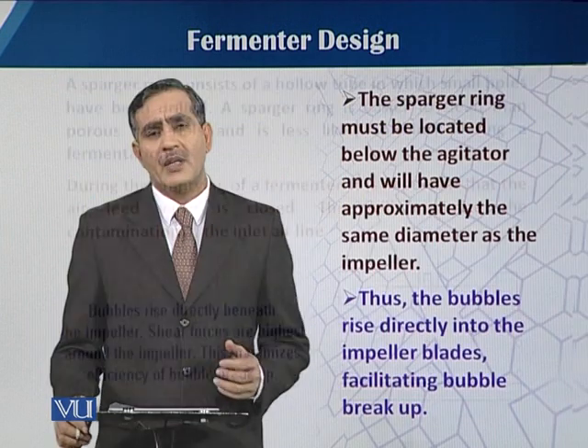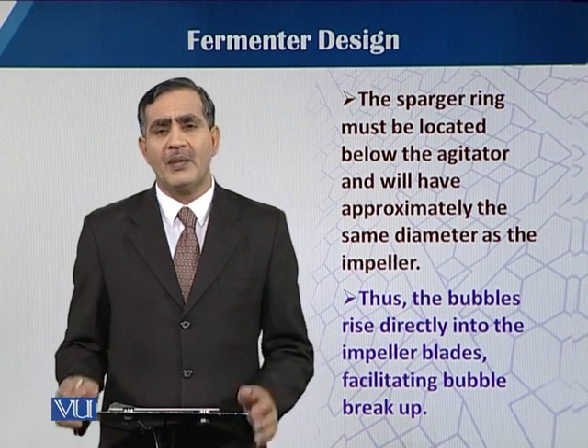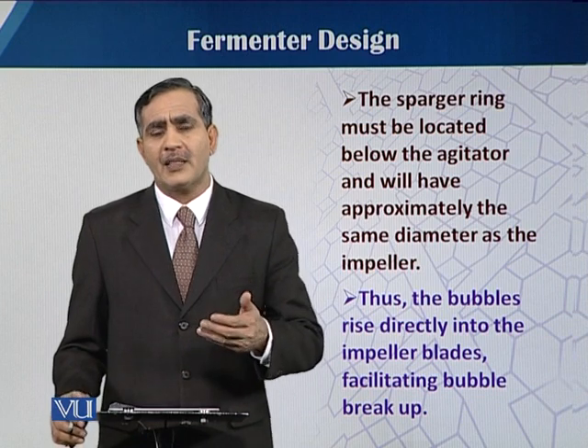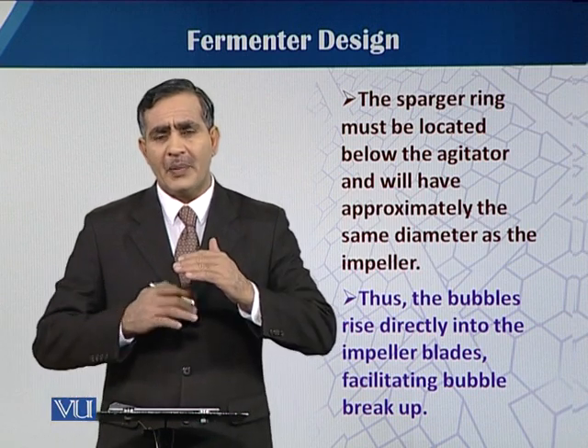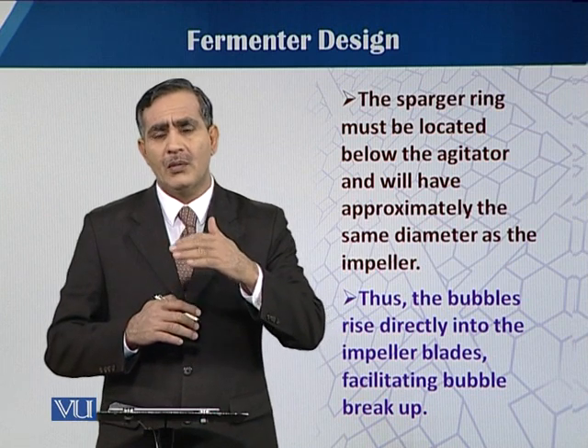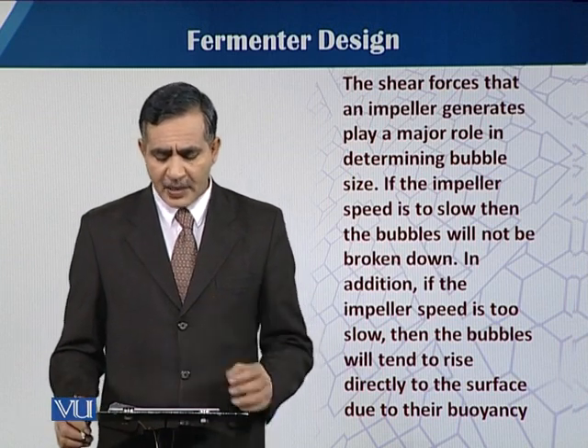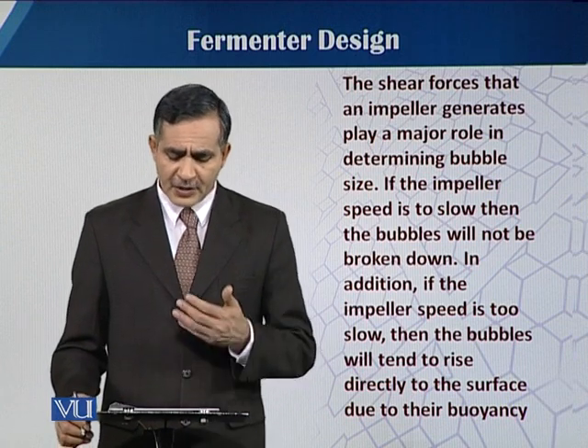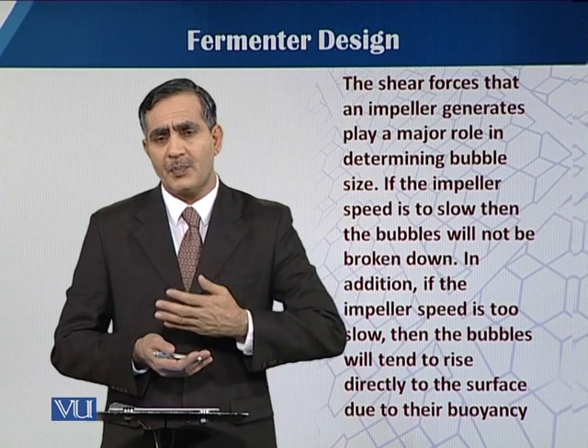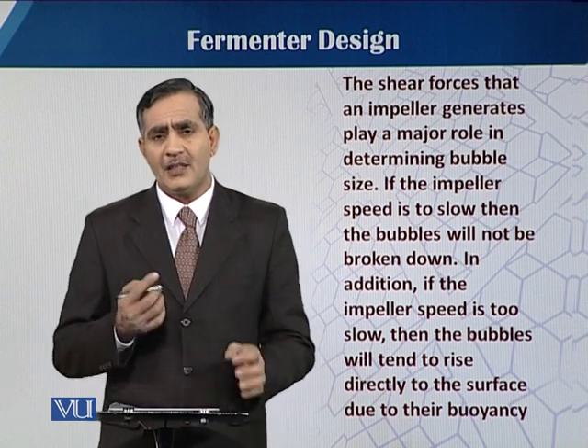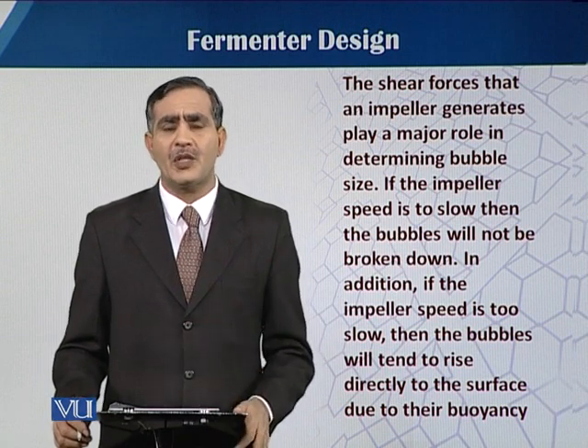The sparger ring should be situated exactly below the impeller. This helps to have direct contact with the air bubbles and facilitates the breakdown of those bubbles into smaller sizes — that is the role of placing the sparger just below the impellers. The shear forces that an impeller generates play a major role in determining the bubble size, and the distance from the sparger to the impeller as well as the speed of the impeller also affect bubble size and distribution.